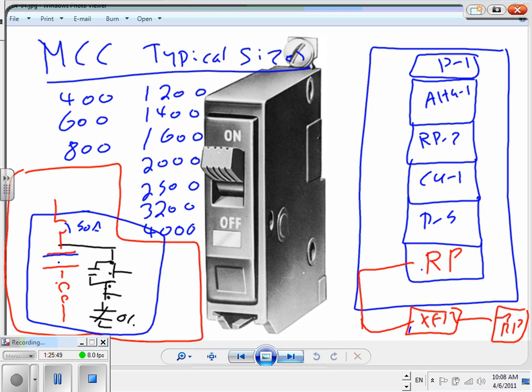So what they do is they use one bucket with just a 100 amp circuit breaker. This one would be only the circuit breaker. It doesn't have all the stuff in it. And they feed it to the panel, and now I have a panel that feeds all my receptacles, a 100 amp panel or a 225 amp panel.